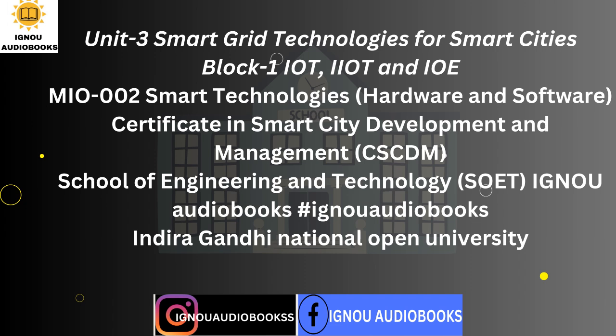Variable speed turbines are used for wind, small hydro and tidal power generation. These generally use AC-DC power conversion where the turbine is arranged to rotate at the optimum speed to extract the maximum power from the fluid flow or minimize mechanical loads on the turbine. The variable frequency power output from the generator is first converted to DC. A second converter is used to convert DC into 50/60 Hz AC. The output of a PV system is DC and therefore a DC-AC converter is essential for grid connection.